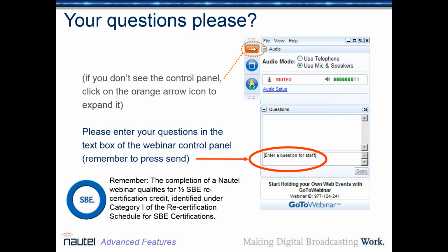Yes, there is a timing input when you go from primary to secondary, but I don't think there's a timing value if it's returning back. And that's actually the reason why we initially configured it so that it wouldn't auto switch back, because if you had an intermittent input, that could be pretty frustrating. But there are a lot of people, and if you don't want to have that, then I'd use the mod loss timeout feature instead. Do you agree with that, Jeff?